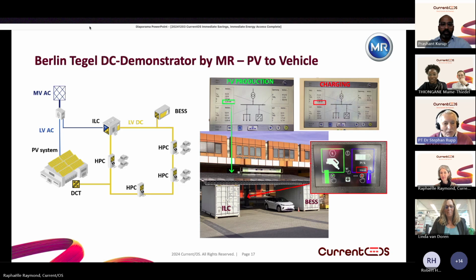If you look at the diagram on the left, we are relieving stress from the AC grid by directly connecting the PV system to DC. It doesn't need to take the trip over AC conversion to get back into the DC grid, because most customers, like shopping malls, bus depots, parking lots, or small industry companies, do have quite huge PV systems in the area of 400 to 800 kilowatts. Sometimes it's difficult to even get a grid connection for such a large PV system.